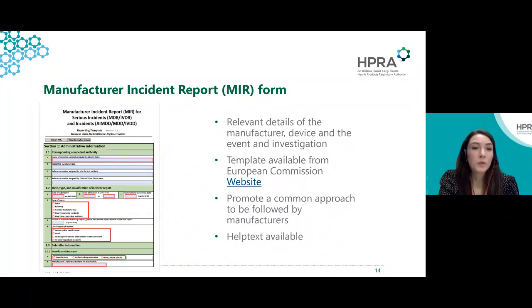So how and who do we report the incidents to? Under the MDR, it states that serious incidents are to be reported to the relevant competent authorities. And this is the competent authority of the country where the incident occurred. There's a template form available from the European Commission, as you can see there on the left, which includes all the relevant fields. And this is used by all manufacturers and competent authorities within the European Union.